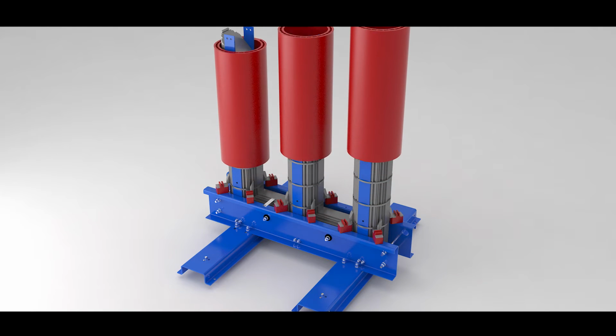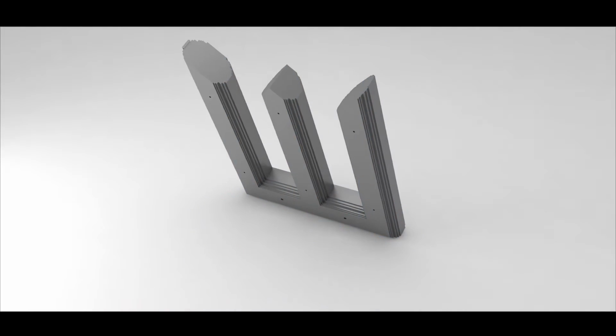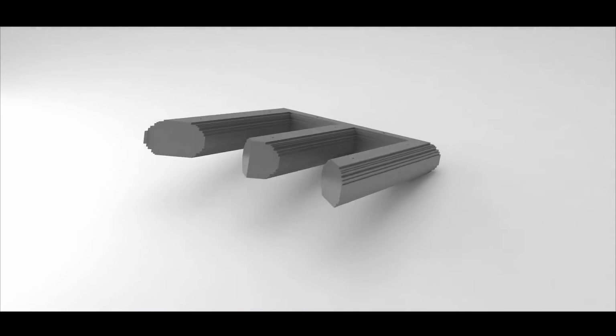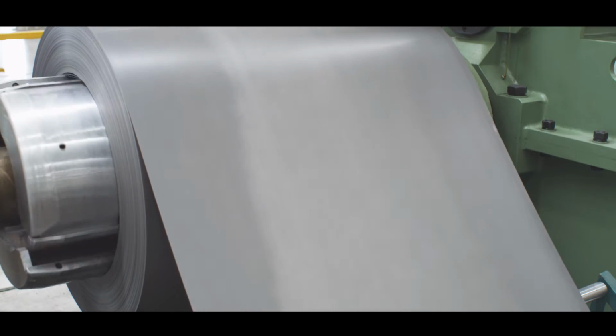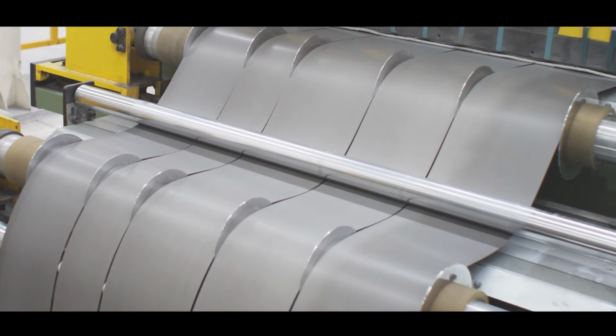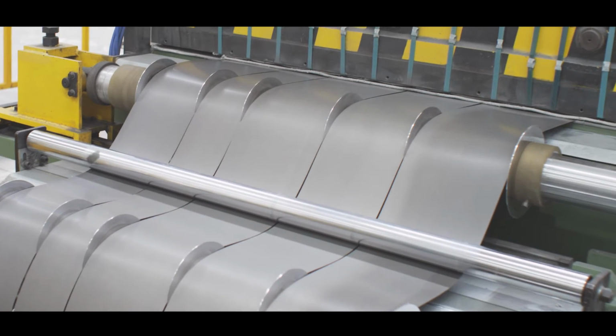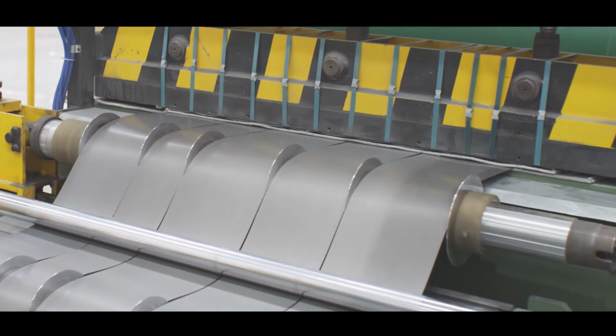When we look at how JST minimizes noise, reduces losses, and realizes high efficiencies, we can start by looking at how the transformer's core is fabricated. By design, the core geometry uses a step-lapped, mitered construction with low-loss core steel as the selected material. As previously mentioned, vertical integration is at the heart of the matter when it comes to the ability of JST to control their own destiny with respect to flexibility in design, lead times, and meeting performance requirements.